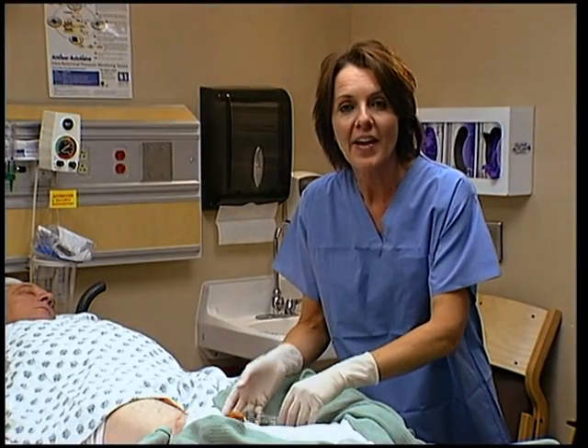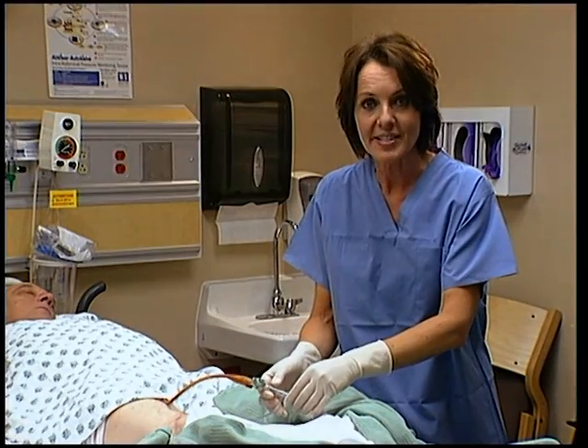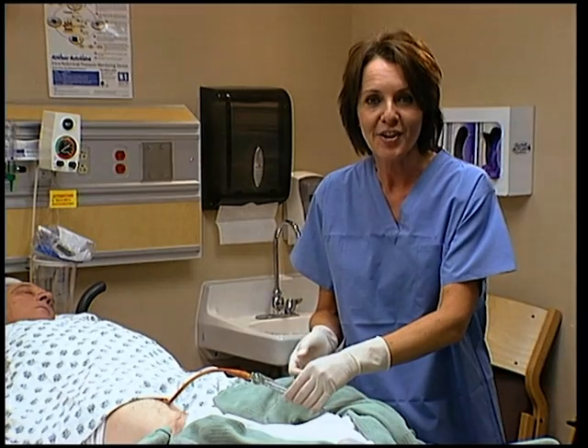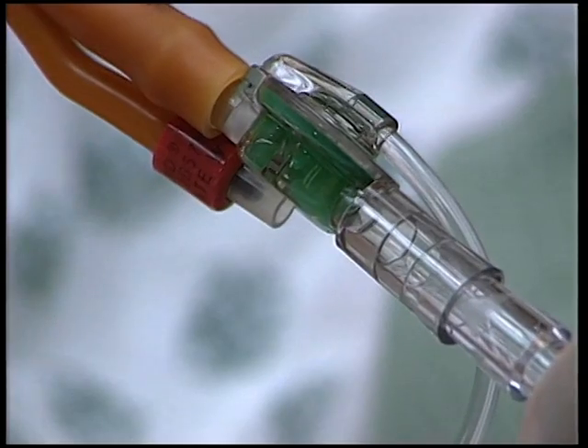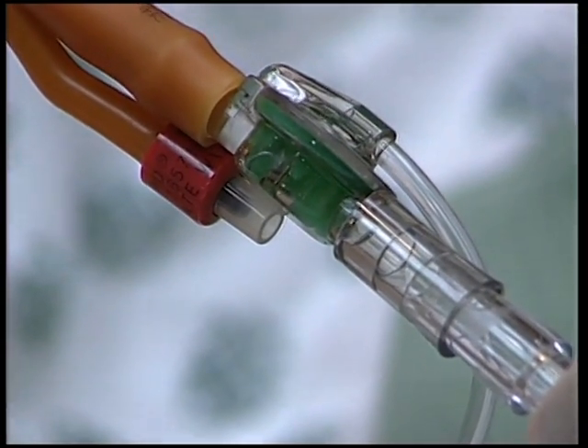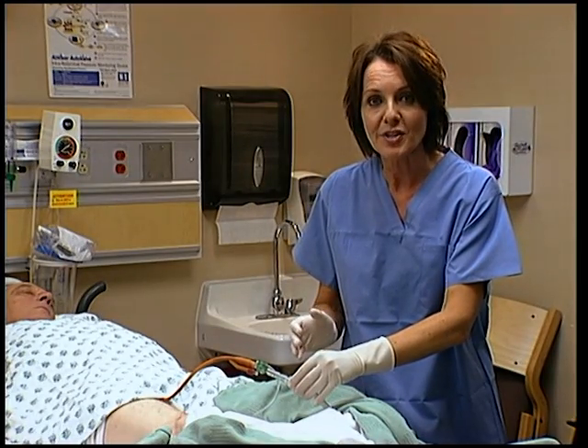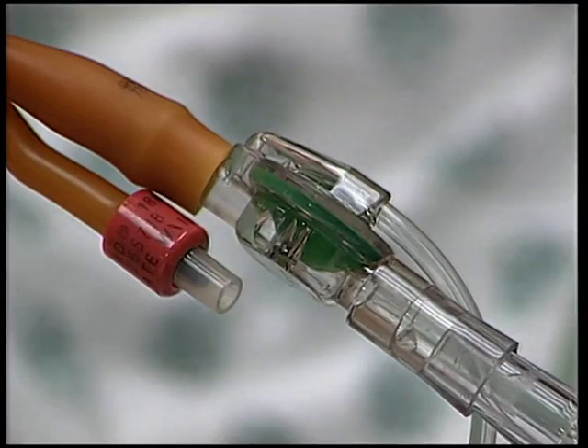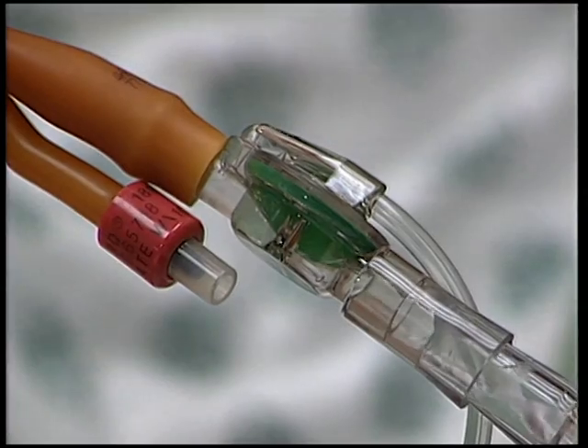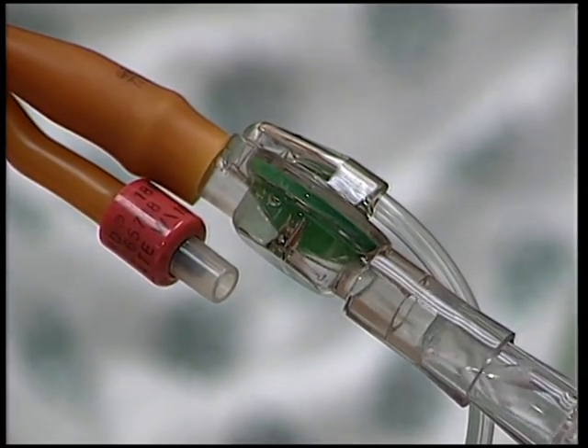The heart of the AbViser is a unique valve that connects directly between the urinary catheter and the drain tube. Once attached, the system never needs to be opened again, maintaining a sterile urinary drain system. When fluid is injected, the diaphragm within the valve is automatically inflated, occluding the drain and directing fluid into the bladder. In this inflated position, you are able to accurately measure intra-abdominal pressure. After approximately two minutes, the diaphragm collapses and the valve automatically opens, allowing the injected saline to drain into the drain bag. The valve remains in this drain position until you infuse saline to obtain your next trending data point.